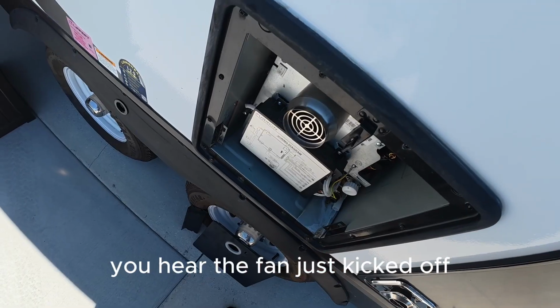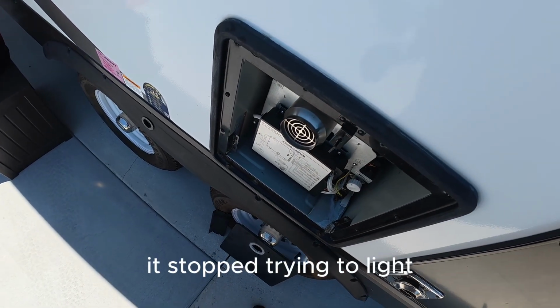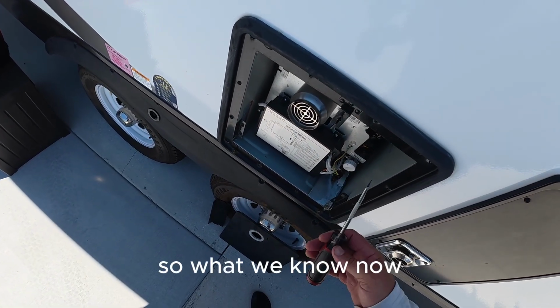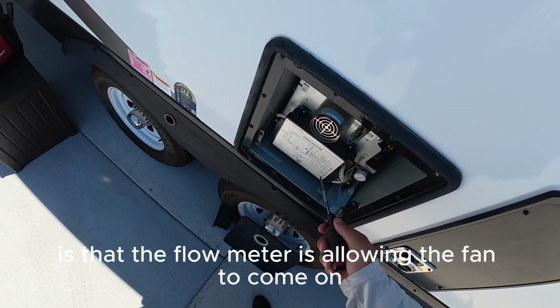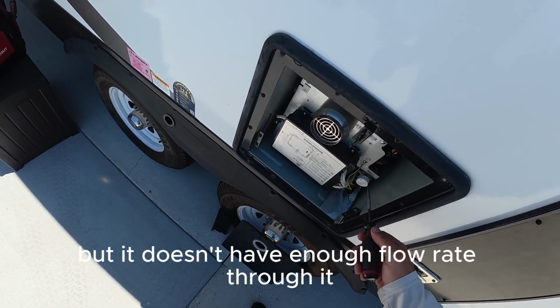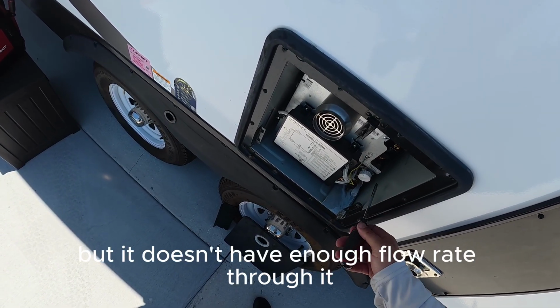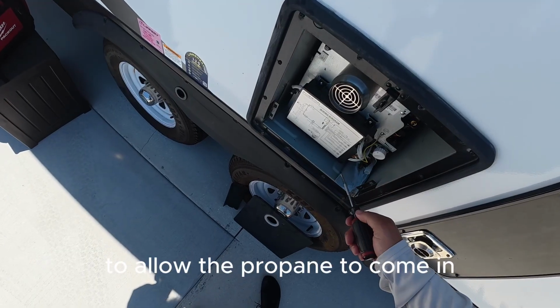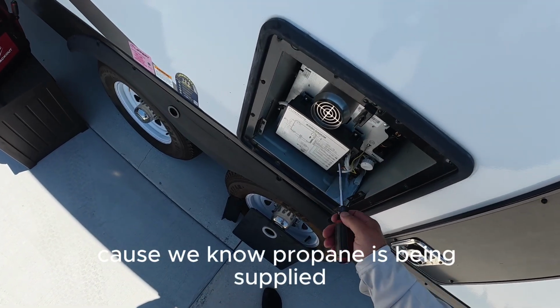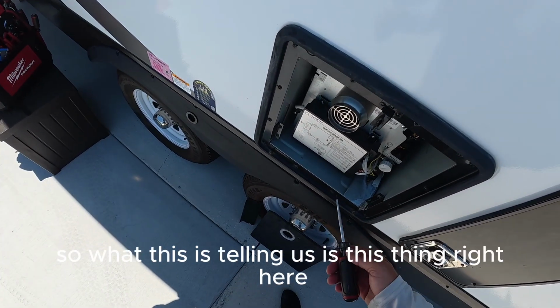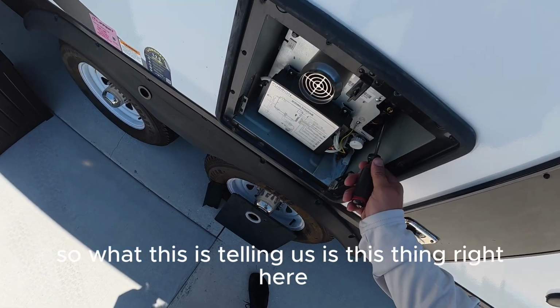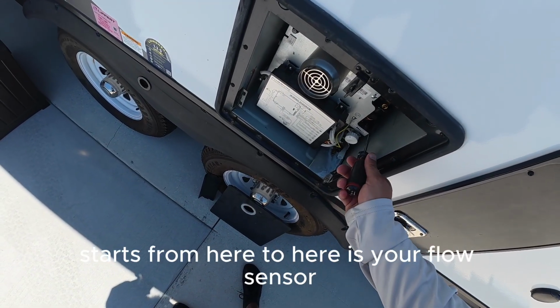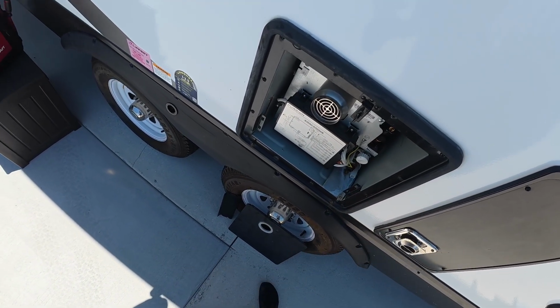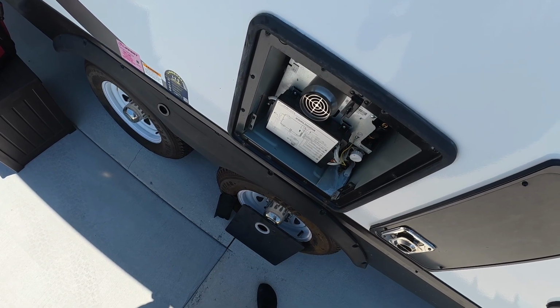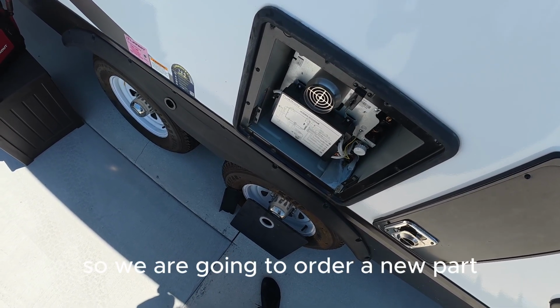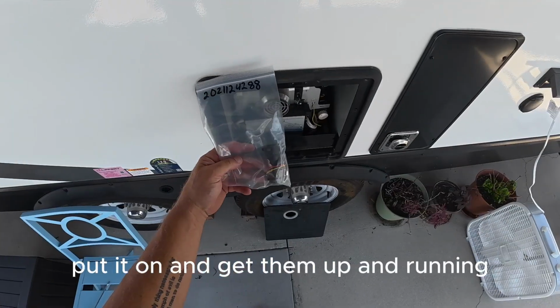Well, it loosened it up, so at least it got the fan. You hear the fan just kicked off. It stopped trying to light. So what we know now is that the flow meter is allowing the fan to come on, but it doesn't have enough flow rate through it to allow the propane to come in, because we know propane is being supplied. So what this is telling us is this thing right here, starting from here to here, is your flow sensor. We have a bad flow sensor. So we are going to order a new part, put it on, and get them up and running. We have the part.